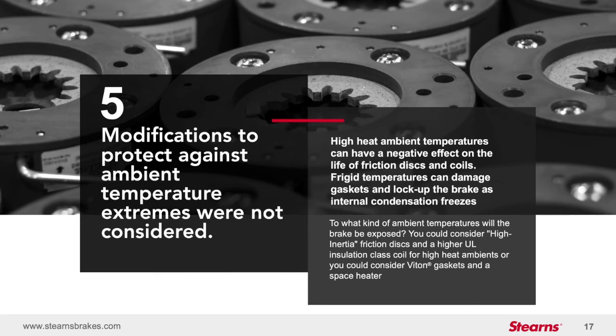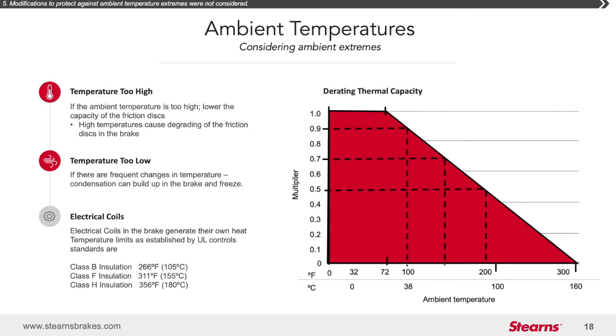Mistake number 5 is modifications to protect against ambient temperature extremes were not considered. In high heat ambient temperatures, you want to make sure you have the best friction disc and coil insulation available because the friction disc and coil are most adversely affected by heat. In frigid temperatures, you want to have the best gasket material to withstand the cold. And if there's fluctuation in temperatures, you definitely want to add a space heater to control condensation inside the brake. Check with the brake manufacturer to find out what options they have for prolonging the life of the brake in extreme temperature conditions. High and low ambient extremes alike can have adverse effects on the brake's performance and service life.